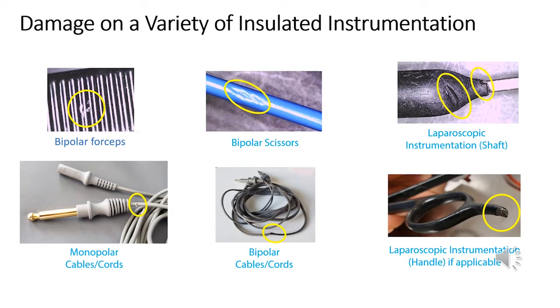In the previous slide, you saw the different types of insulated instrumentation and devices. Now you can see in this slide what type of damage can happen to those specific insulated instruments. For the bipolar forceps, you can see there's a nick. The bipolar scissors, you can see there's a gouge. For a laparoscopic shaft, you can see at the distal end that it's peeling away and it's scratched. For the monopolar cable and cords, you can see there's a big nick towards the proximal end where it hooks up to the equipment. And here's another cord, bipolar, where it's actually split halfway through the cord. And then a laparoscopic insulated handle, where you can see at the very distal end of that handle, there's a big piece of insulation missing.